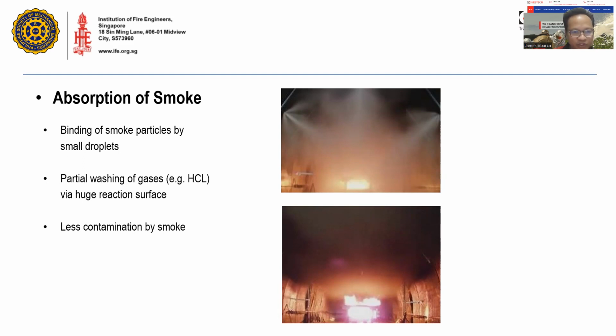But for a water mist system, there is a binding of smoke particles by the droplets, as you can see from the figure itself, and also a partial washing of gases, via a huge reaction surface. There will be less contamination by smoke when water mist is applied, because you discharge your mist from the nozzles on top, and the smoke is always going up from the fire. That mist will have an absorption effect on the smoke.